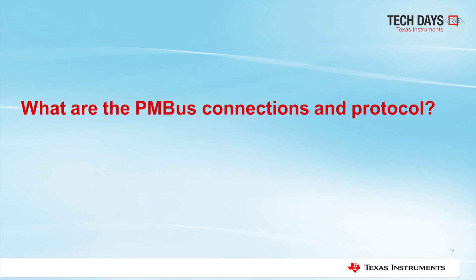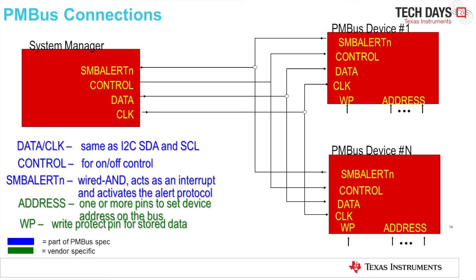What are the PMBus connections and protocol? These are the PMBus connections. The data and clock are the same as I2C — SDA and SCL — and these are bidirectional. The control, which is basically the PMBus enable for on/off control. The SMB alert, which is a wired-AND signal and acts as an interrupt and activates the alert protocol. Also the address, which is vendor specific, using one or more of the IC pins to set the device address on the bus. And also the WP (Write Protect) pin to protect the stored data.